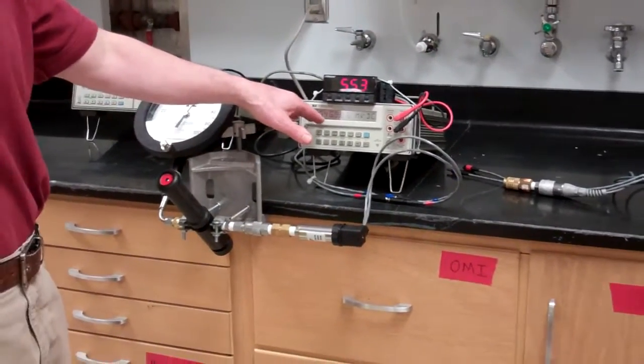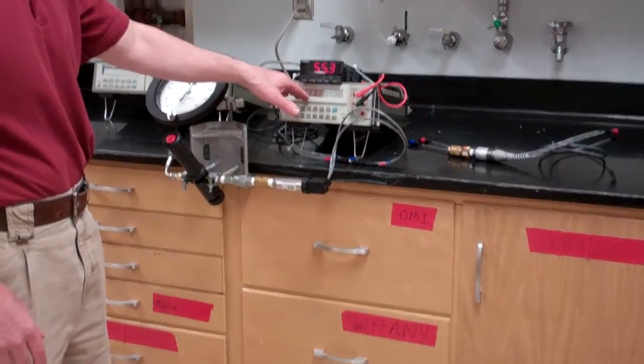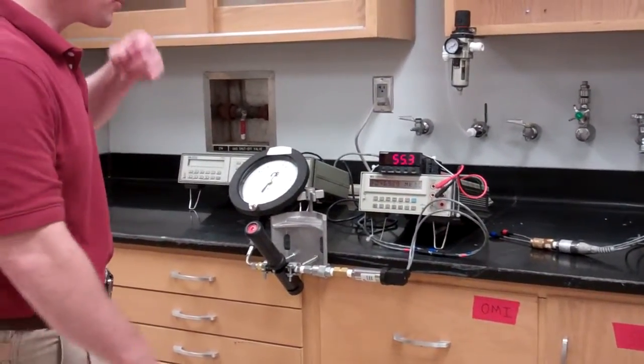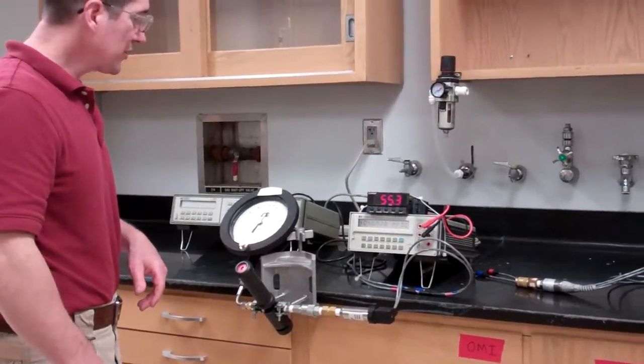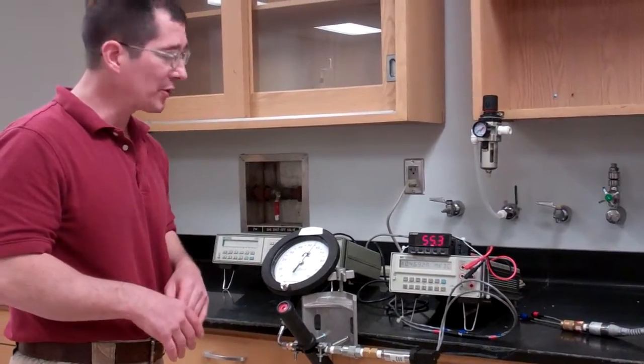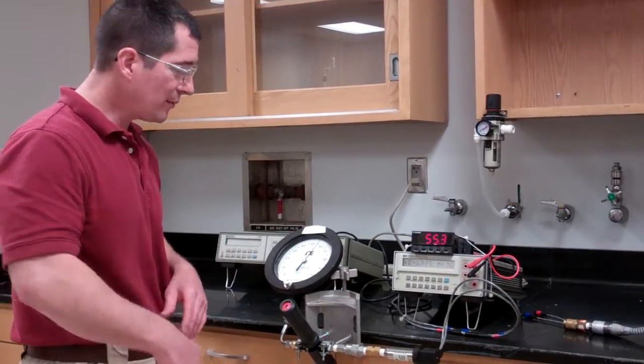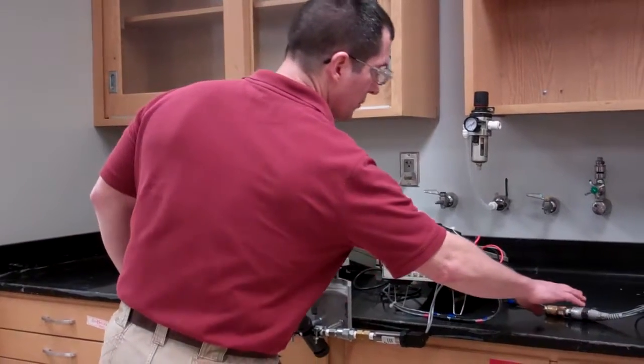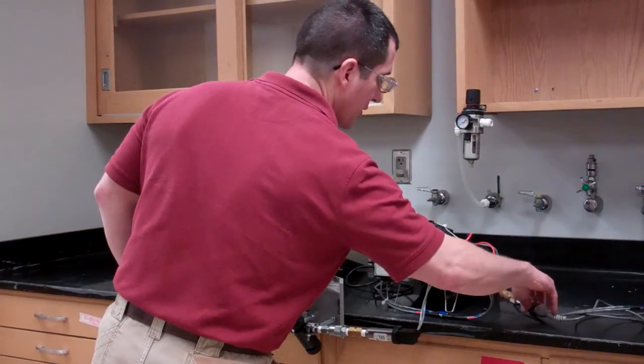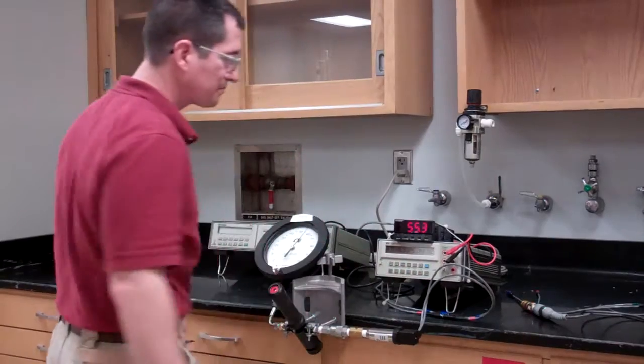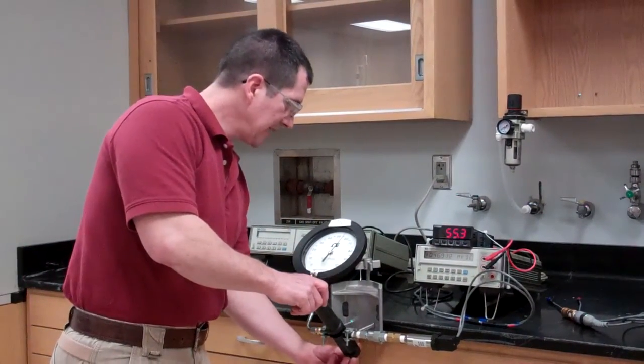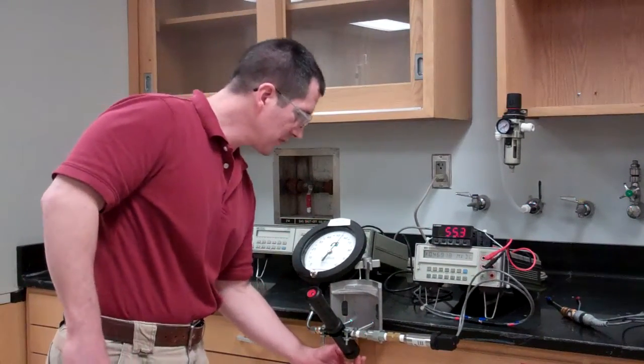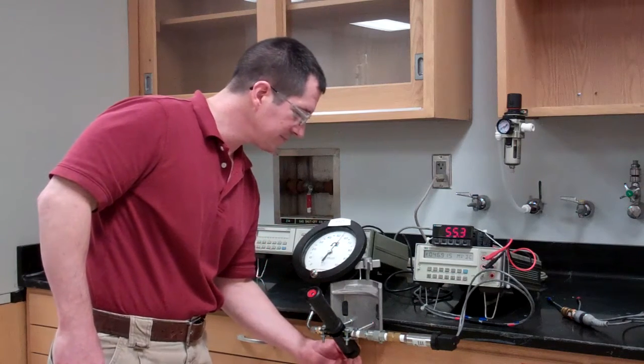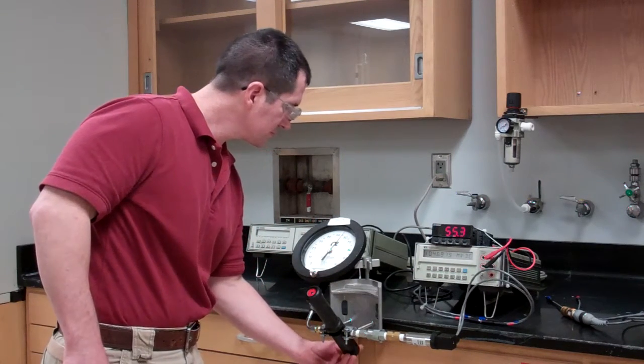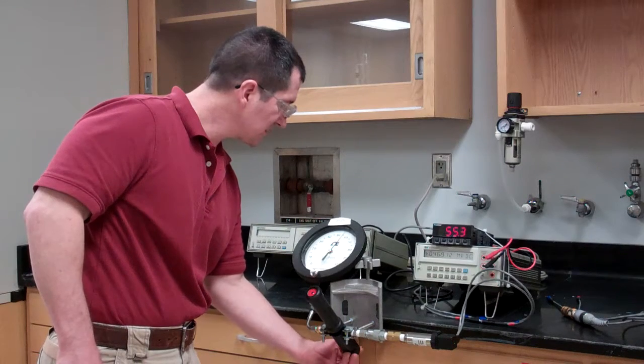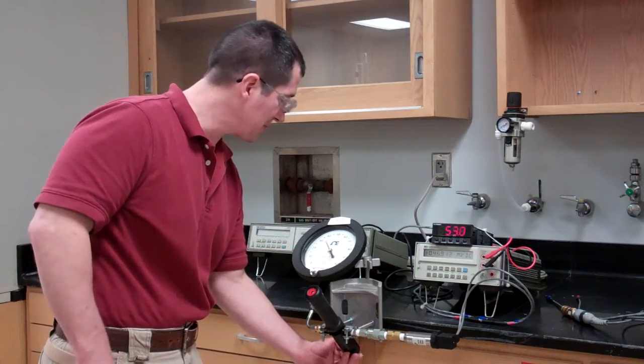And you can also see that the multimeter is giving us a signal, millivolts DC. That's the output of the transducer. So you're going to test this at various levels, and you also want to look at repeatability. And then you'll switch the pressure transducer to the other one and calibrate that one as well. And to bleed out the pressure, you just unscrew this knob here in the back. And so before you switch transducers, that's what you want to do.